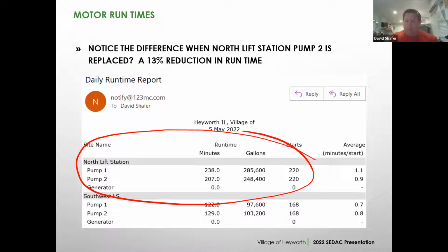Well, the next full day of runtime, I get my report, and you can see pump two was the new pump that was dropped in. My runtime was 13% less than the other pump already in there. They're the same model, exact same specification, same horsepower, same impeller, same manufacturer. So then the question is, why is my runtime different on pump one?